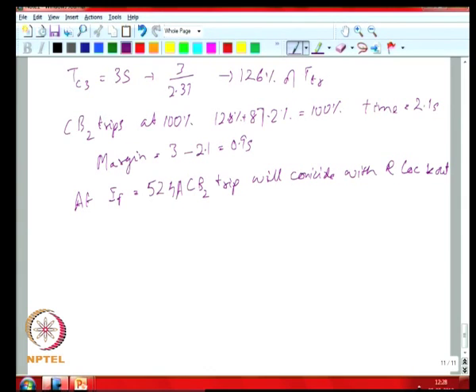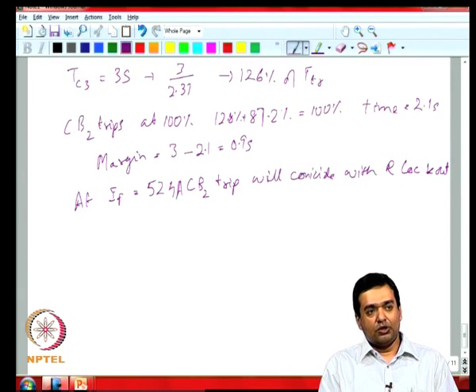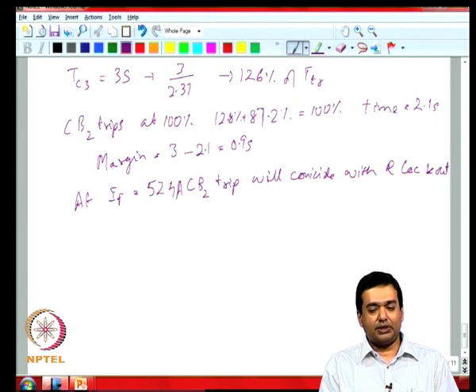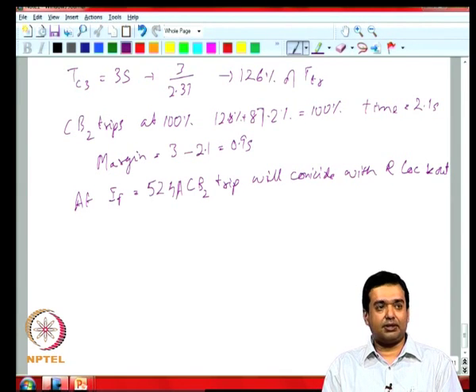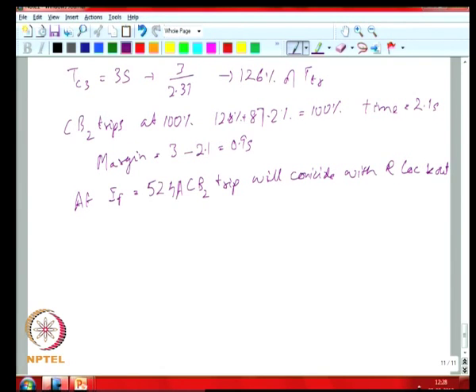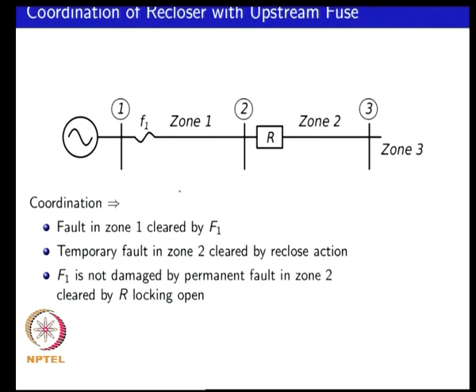In typical protection coordination practice, you design upstream protection before deciding on downstream settings. In some situations you need to look at the entire system to decide on settings so you do not have nuisance trips. Another situation is coordinating an upstream fuse with a downstream recloser — for example, a backup protection fuse operating with a downstream recloser.